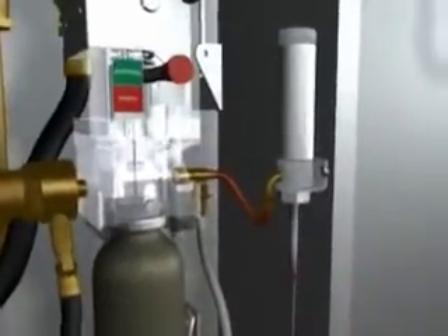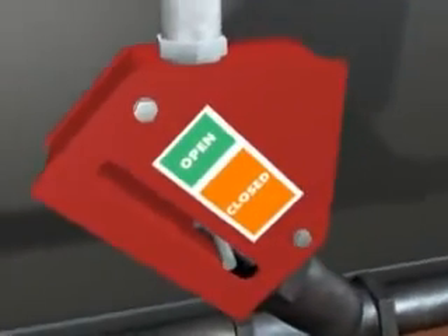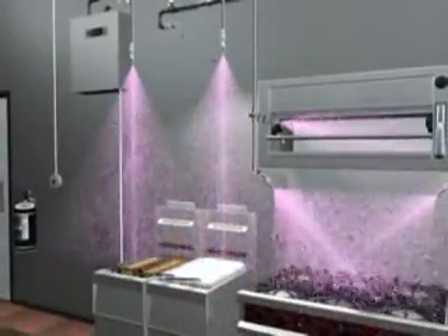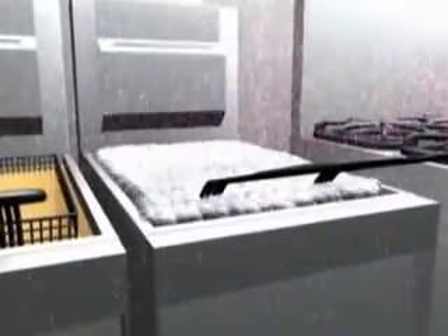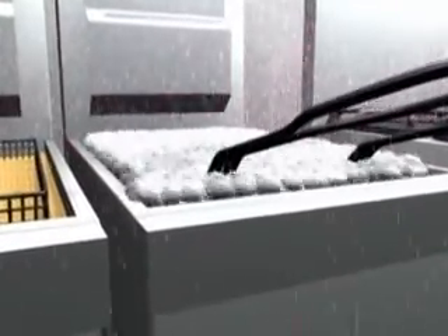Simultaneously, an air cylinder is pressurized, tripping the Ansul mechanical gas shutoff valve. The discharged chemical reacts with the hot grease to form a vapor securing blanket to help prevent fire reflashes.